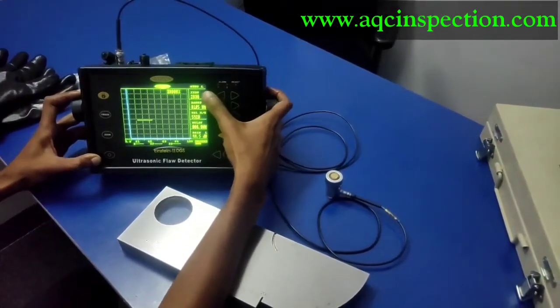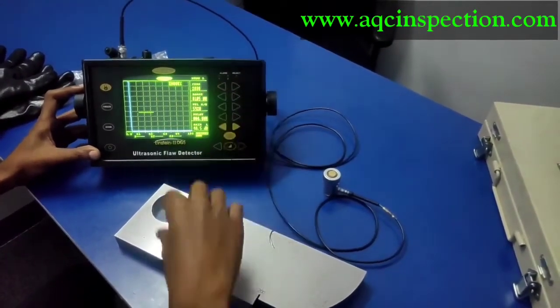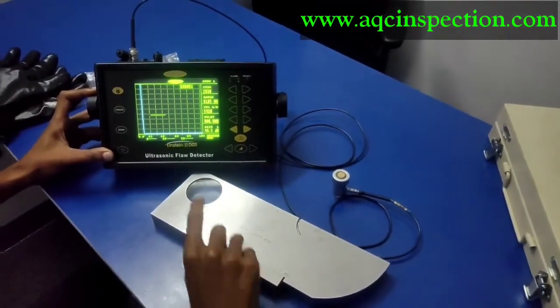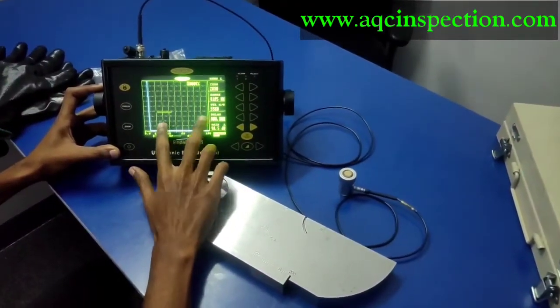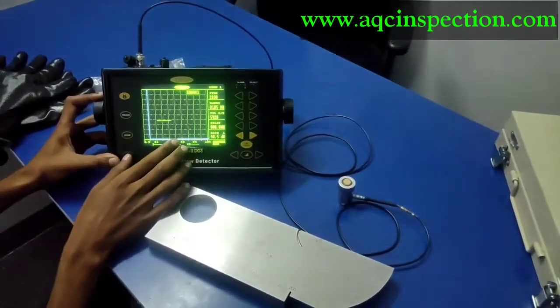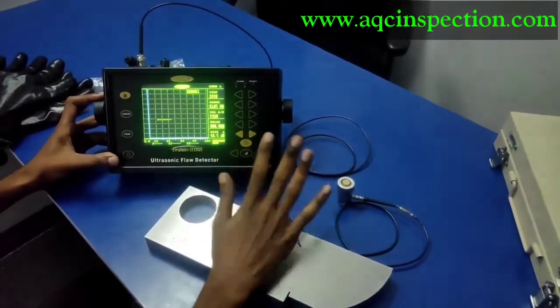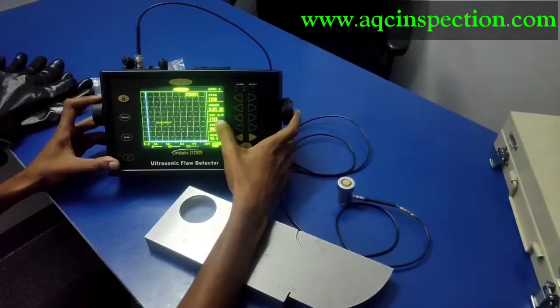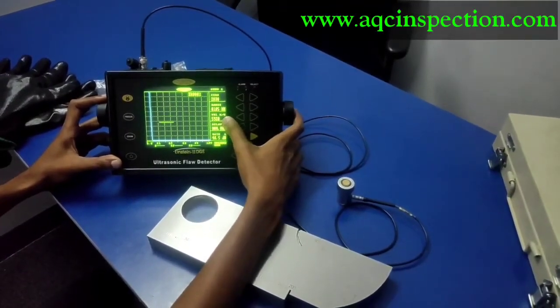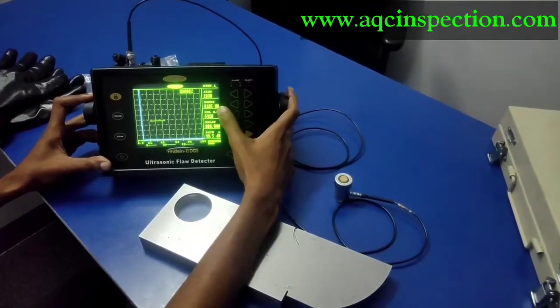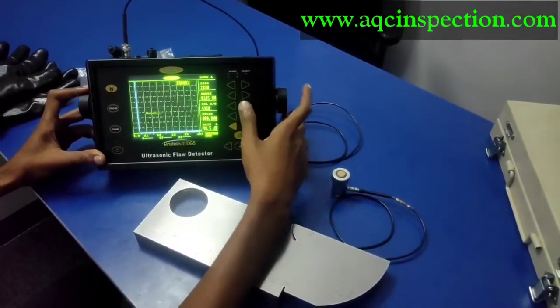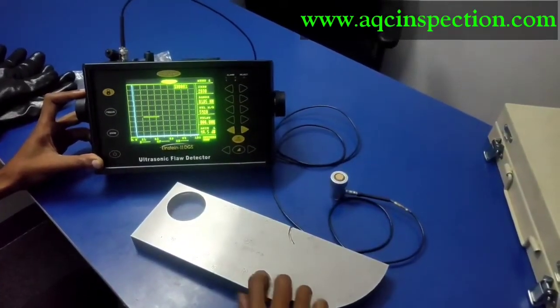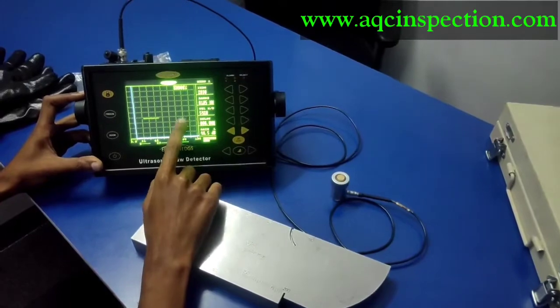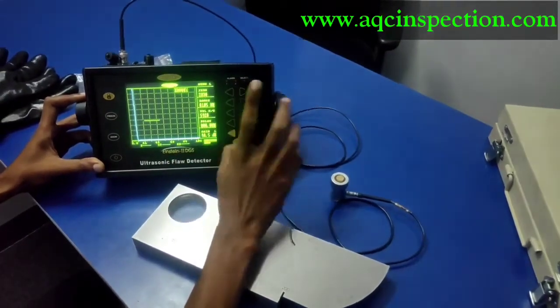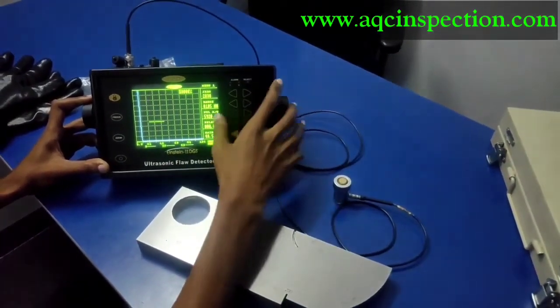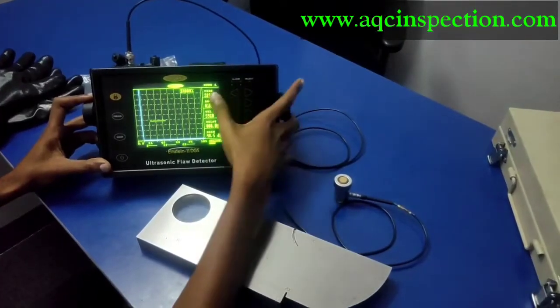This right here is the zero of the probe. We have to calibrate this to 25 mm, which is a known thickness, so that we get 4 backward echoes properly. Once we calibrate this, then we can do the inspection. This is the velocity for steel, which is 5920 meters per second. Then the range I have set is 105 mm because I am going to set 4 backward echoes, which is 25, 50, 75 and 100. So I have just put 105 mm instead of 100 so that I can see the backward echoes clearly.